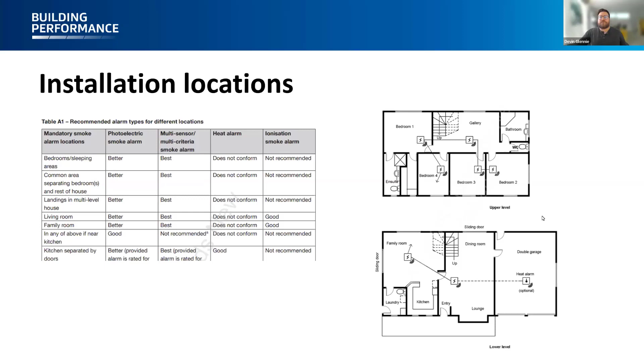Visual alerting devices—simply a flashing light or some kind of visual alert that the fire alarm is going off—are for deaf people and those who are hard of hearing. These already existed in the alarm for noisy environments, but the specifications have been expanded to apply throughout the building, not just in noisy environments like plant rooms. Wireless detection technology is now allowed, along with network systems and duct smoke detection. All these sections in the alarm standard have been expanded. The committee looked at new industry technology available out there, and made sure the standard is up to date with current technology so we can keep up here in New Zealand.